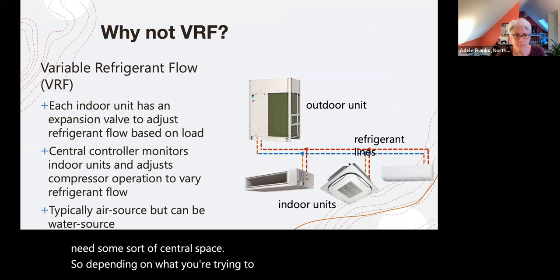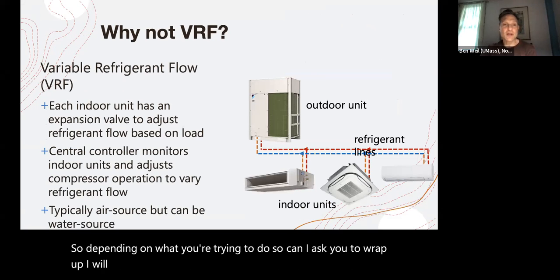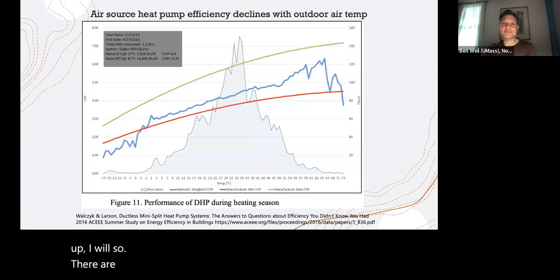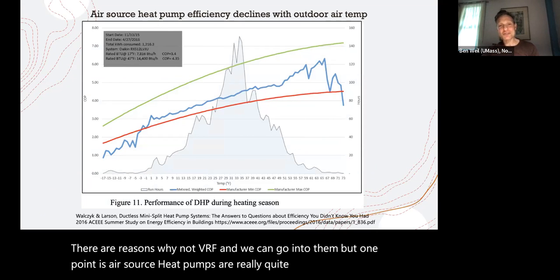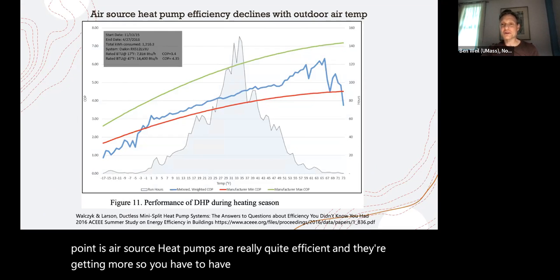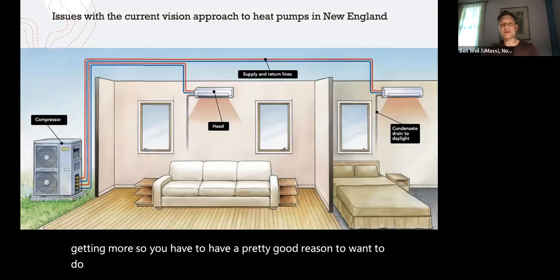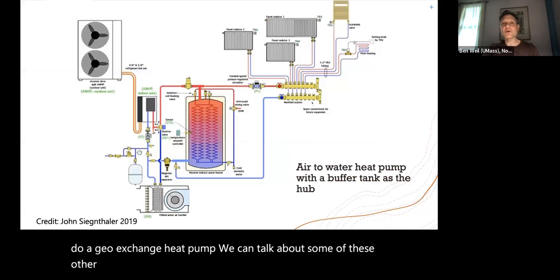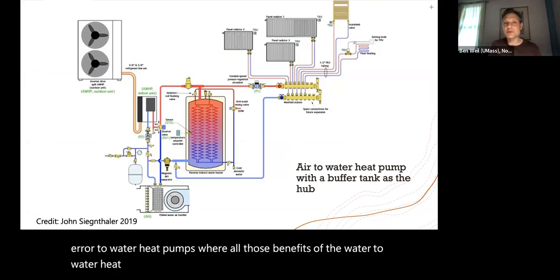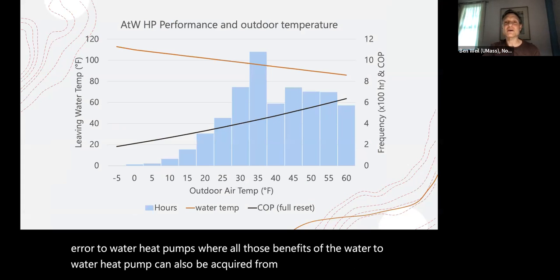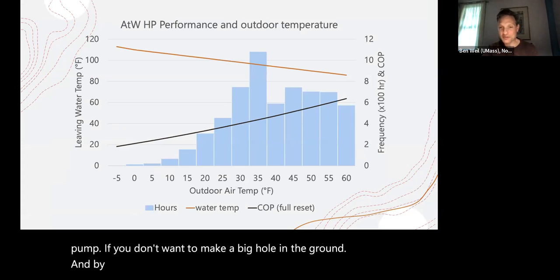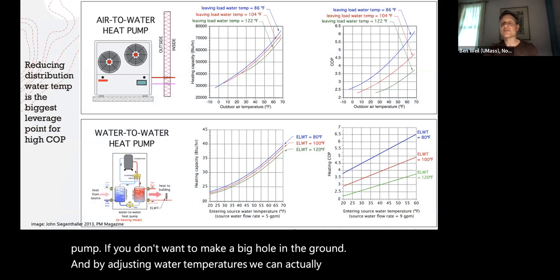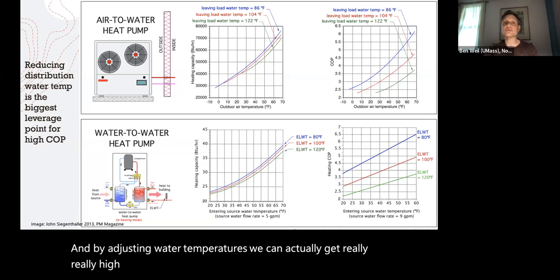Can I ask you, yes, to wrap up? I will. So there are reasons why not VRF, and we can go into them, but one point is air source heat pumps are really quite efficient and they're getting more so. So you have to have a pretty good reason to want to do a geo exchange heat pump. I'll just skip some of these other things, but I will point out that there are air to water heat pumps where all those benefits of the water to water heat pump can also be acquired from an air source heat pump if you don't want to make a big hole in the ground. And by adjusting water temperatures, we can get really, really high efficiencies comparable to a ground source heat pump using an air source heat pump.